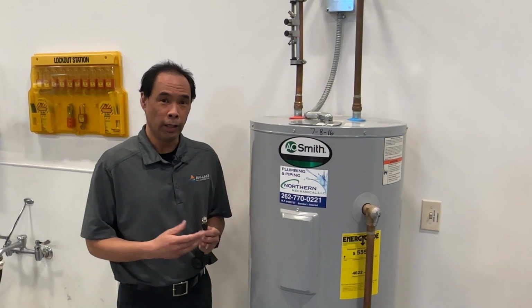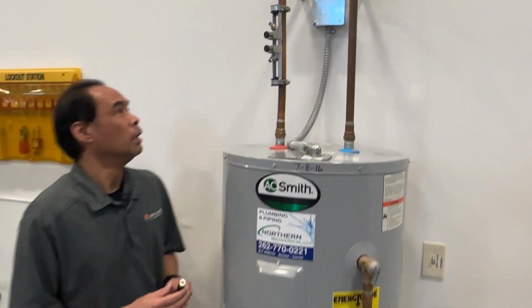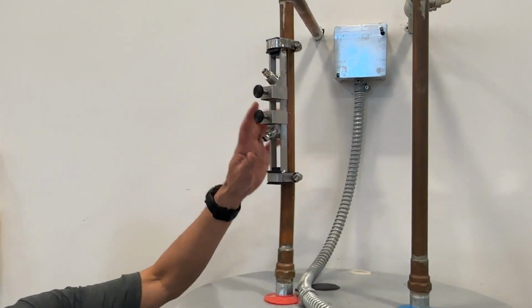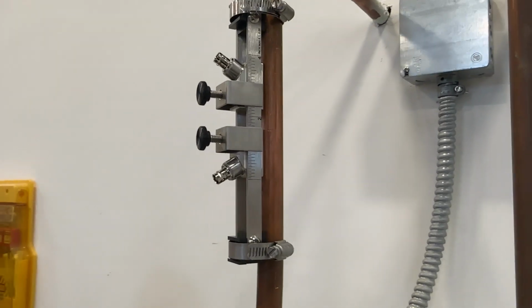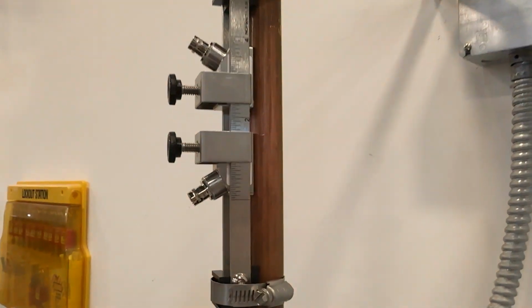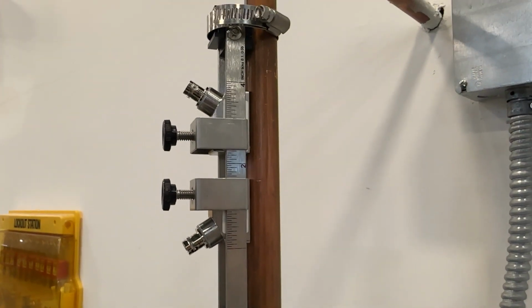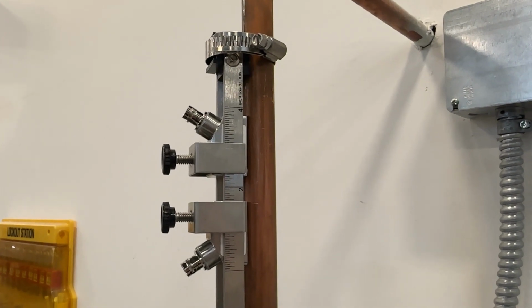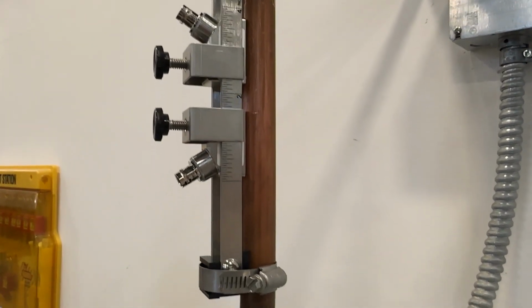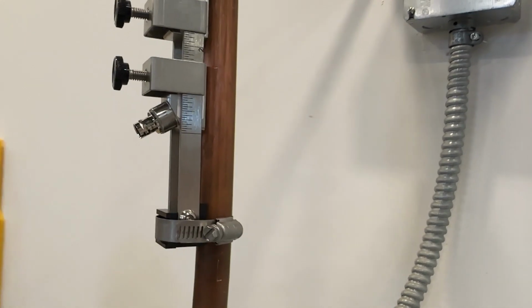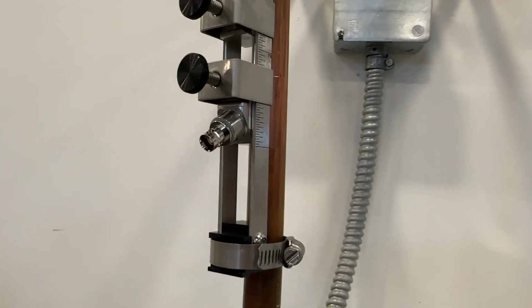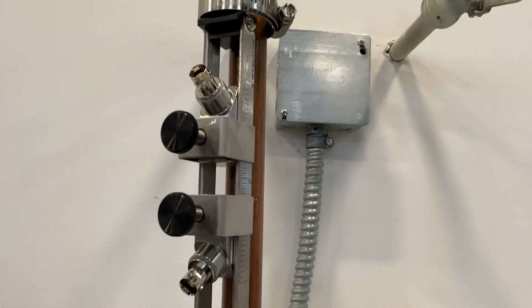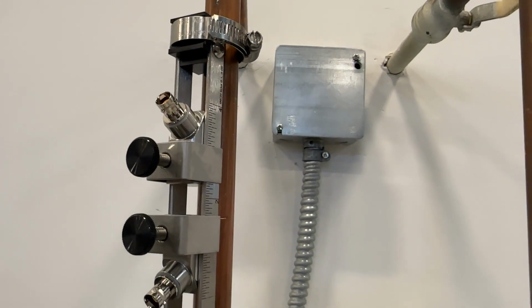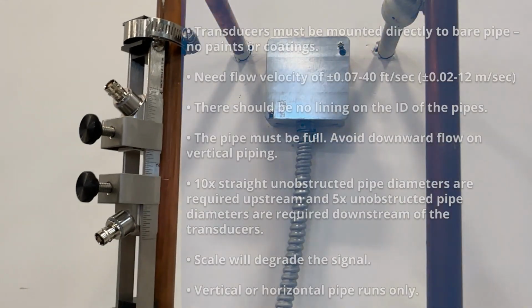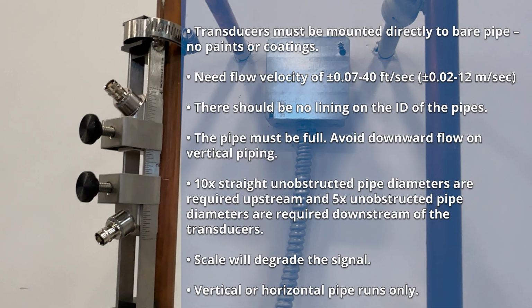Here we have our installed hardware. As you can see, the transducers have the ports pointing out and are clamped on as shown, making sure we have 10 times pipe diameter upstream and 5 times diameter downstream to bare pipe, with lubricant on the transducer face to get a good electrical signal.